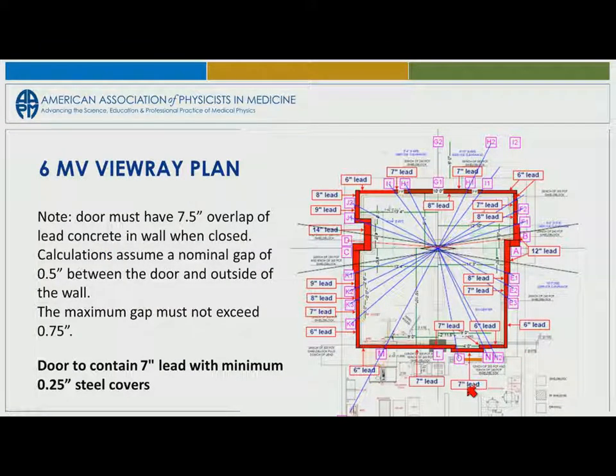Here's a Viewray room. The door must have 7.5 inches of overlap between the lead and concrete in the wall when closed. And we also assume that you've got no more than 1/2 inch gap between the door and the outside wall. And then the door in this one has 7 inches of lead in it. Again, it's only 6 MV, so you have no neutrons to consider with a Viewray. It's just a 6 MV unit. But this one's going into Miami. And so it's our first Viewray with the 6 MV in it. So it works real well.